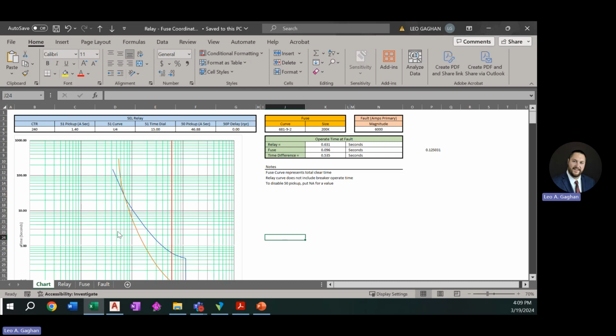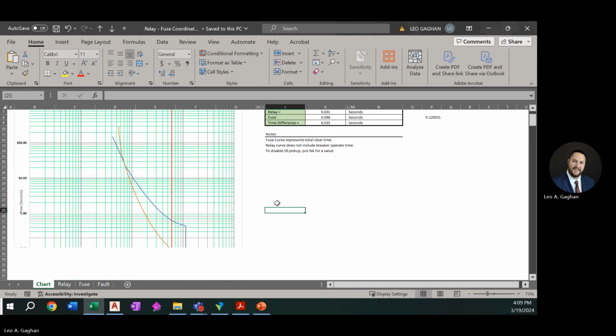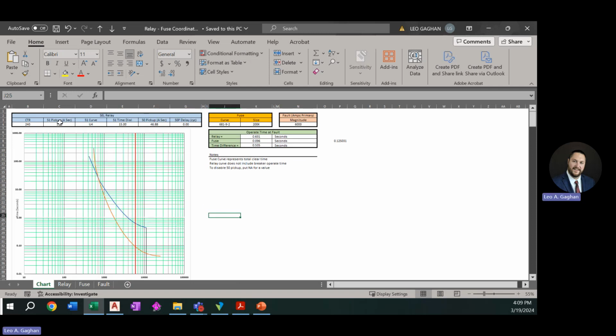So we can see here, try zooming out, our blue curve is our relay, which will trip a breaker. Our orange is actually a fuse curve. It's the total clear time here. It would have been tough for me to put a minimum melt into Aspen, so I didn't do that. And again, breaker trip times don't include things like breaker operate time and such, which, like I said, just like Aspen, it's fairly realistic here.